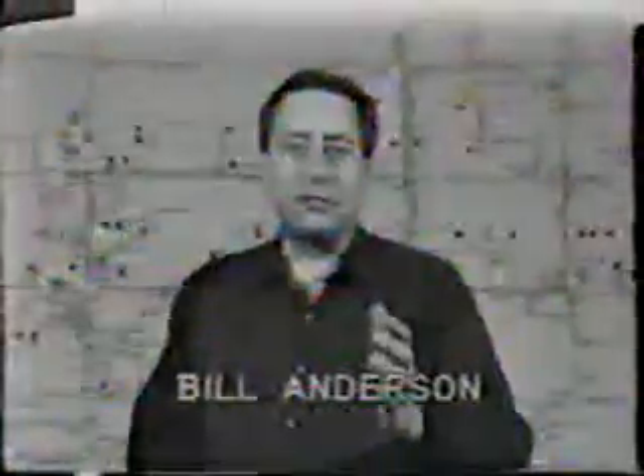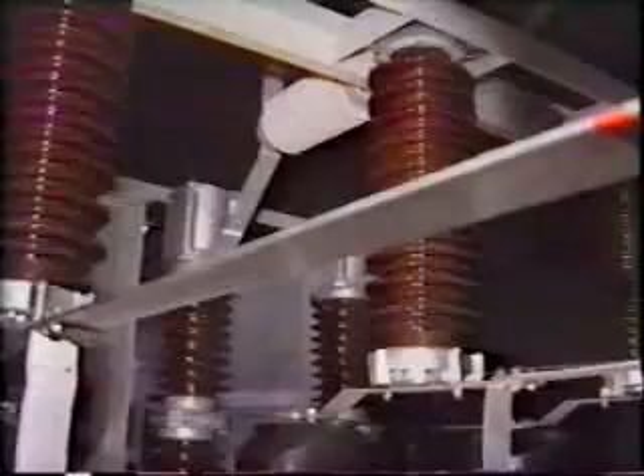When any protective scheme is newly installed, it must be thoroughly checked and tested before placing it into operational service. Commissioning covers a very wide range of activities, as we shall see. In many cases, the protective scheme forms part of a completely new power installation, or perhaps an extension to an existing substation or generating station.